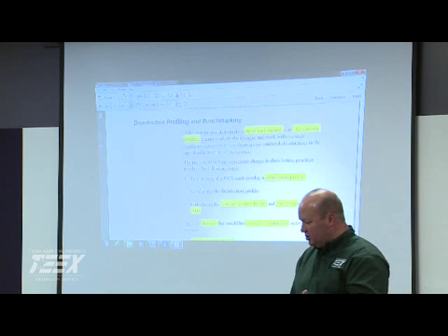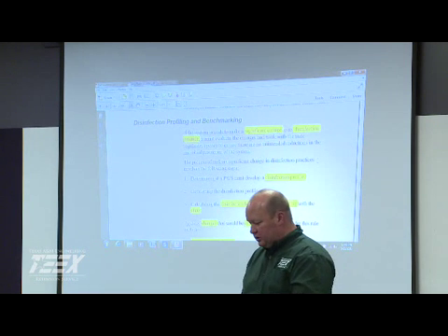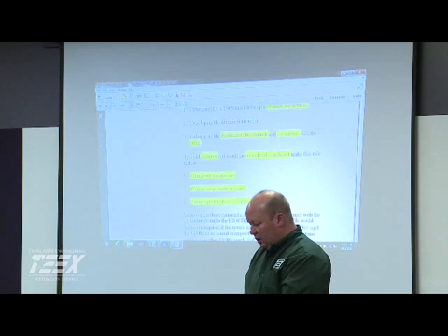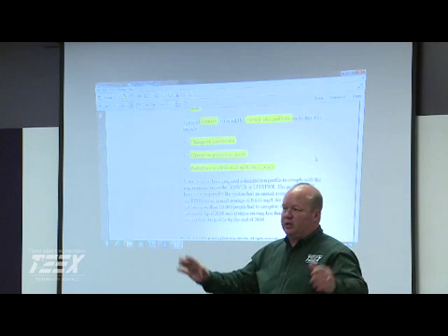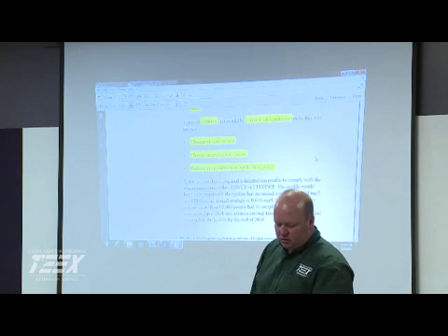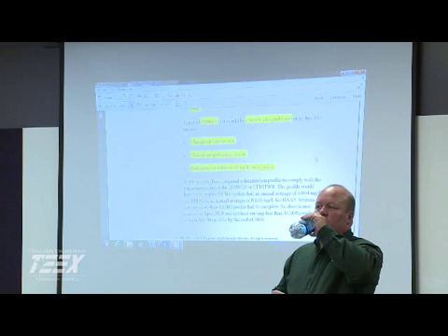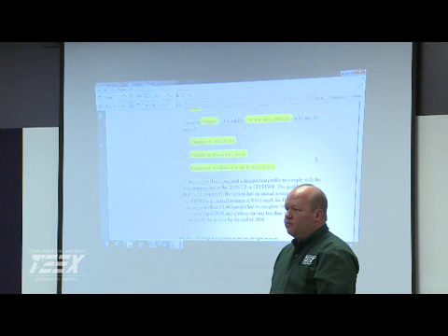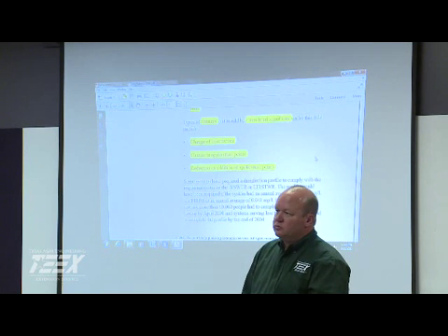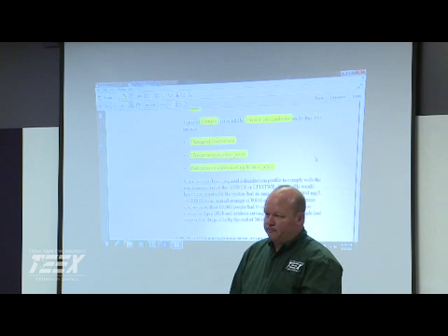What are our significant changes? We're looking at the types of disinfection and the application points. Those are the 2 big ones. So, do you do it on a regular basis, disinfection profiles? Is it you establish one and that's basically it? We look at it more of a CT calculation type. Some systems do CT calculations daily. We've allowed that you can do a worst case CT calculation, and if any of those parameters are exceeded, you do the CT calculation for that day. But no, we don't have systems doing a disinfection profile all the time.